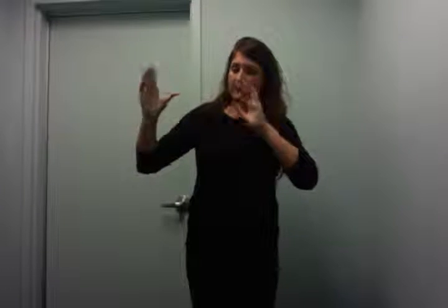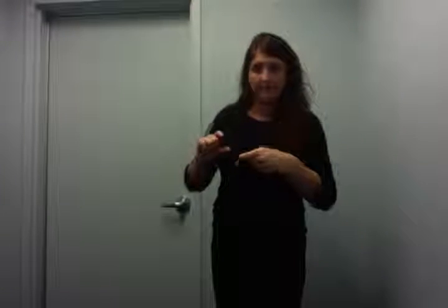What's the main difference between the two, though, is this. On one of the thermometers, I took a bunch of this filter wool, or cotton basically, and wrapped it around there, and then connected it with some rubber bands. These are called the bulbs of the thermometer, the silver parts down here on the bottom. What they do to measure relative humidity is they take this bulb here and get it wet. This is the wet bulb, this is the dry bulb.